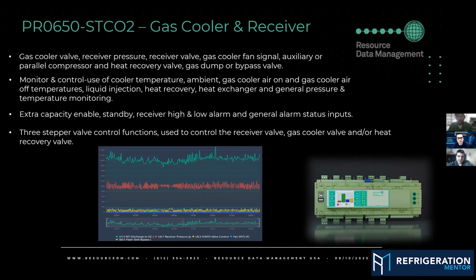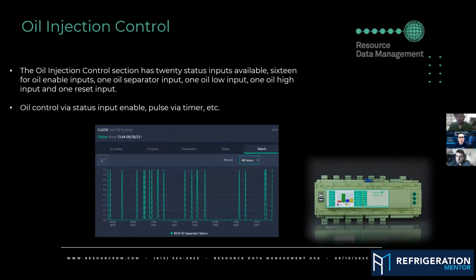Yeah, cool. Your only limitation really: if you had 2 steppers on your main board and you needed that third, then you'd have to buy a little stepper expansion module. Or if you wanted steppers that had auto close, we have stepper expansion modules that have auto close, so you don't need to run an uninterrupted power supply. They just have a little capacitor on board where they detect a failure in the power, close the valve down, and then they go to sleep too. Yeah, because I see on larger systems where they may have redundant valves. So they might have 2 flash gas bypass valves and 2 high pressure valves. That's where you would have to have that extra module or expansion pack for the other valve.